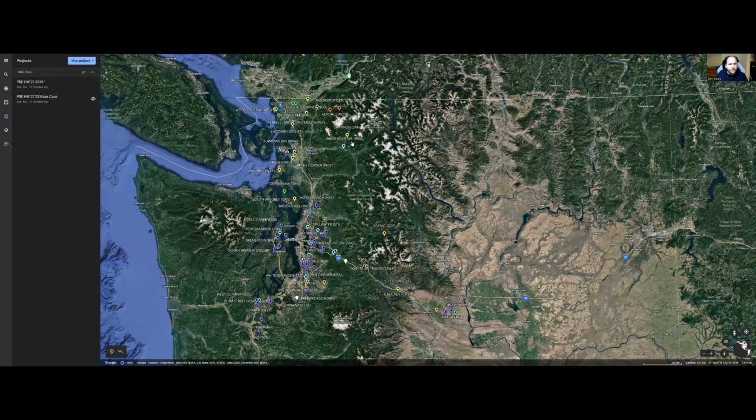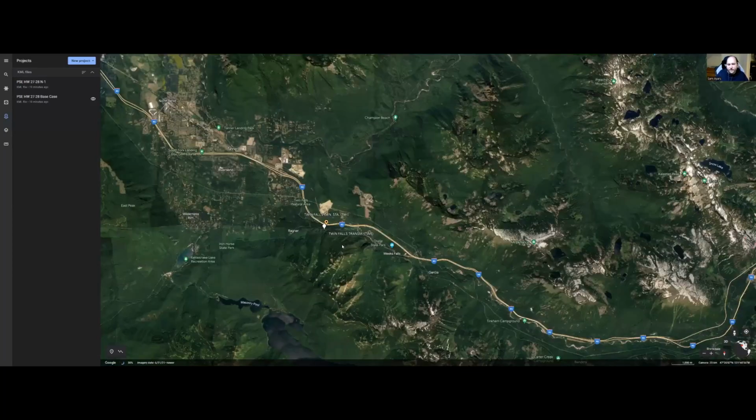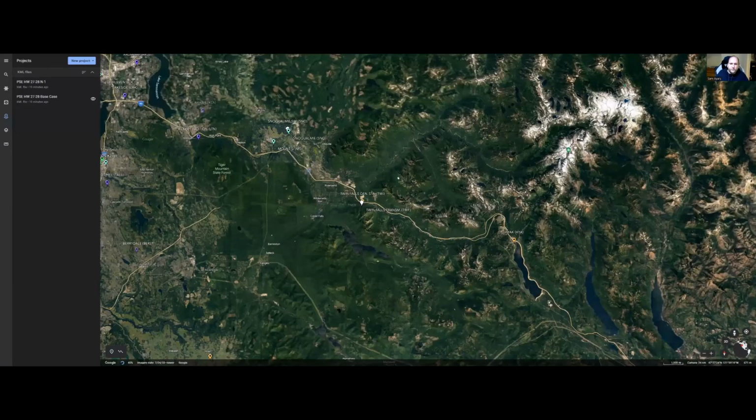And here we have the map itself for all counties. This is the base case. As you see, there's a lot of purple, which means there's 600 or more megawatts available there. There's not too much red except for up here. I also left in some error markers, such as this one right here. This just alerts the team if they have a mismatch between the substations that it's expecting to see and the substations they're putting into the code. So it helps them spot if anything went wrong.